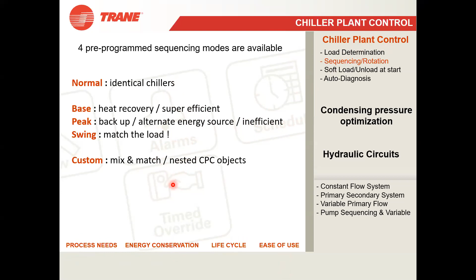Now next, I told you about swinging, and I will make you understand. Sequencing is what we also call swinging. Suppose this is an example: one building's maximum load is 1200 TR. You have 3 chillers: one 200 ton, one 500 ton, another 500. When you are switching on the first time, it will first switch on the 200 TR chiller. Because this is the smallest capacity, and when your office is getting started, a minimum number of people will be there, and gradually it increases, right?